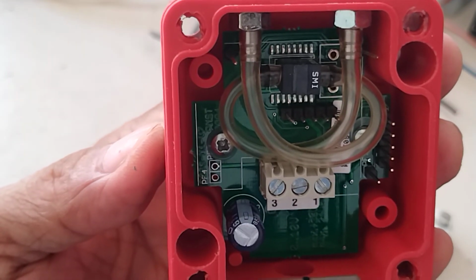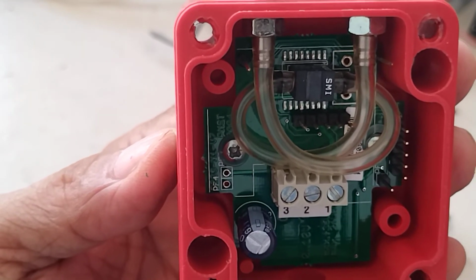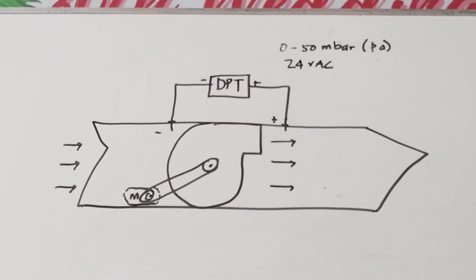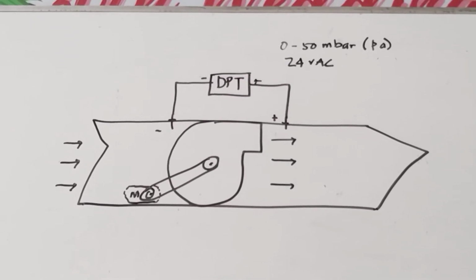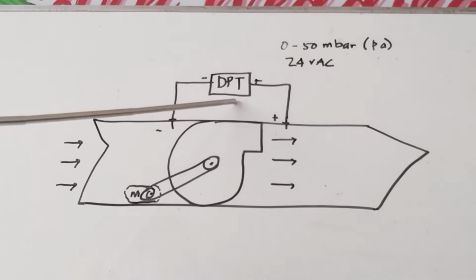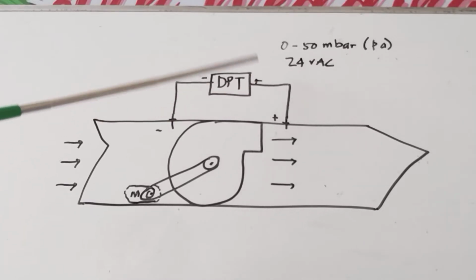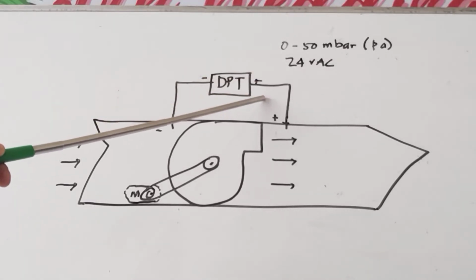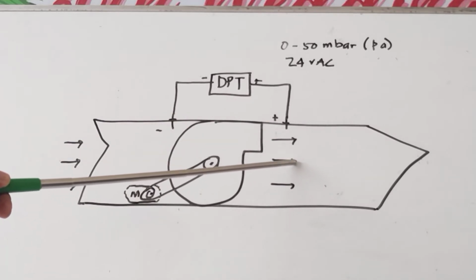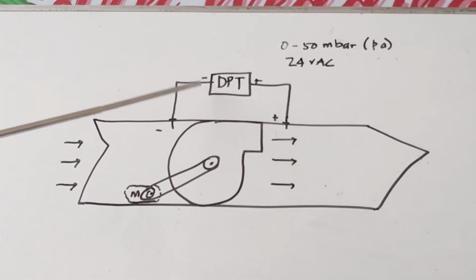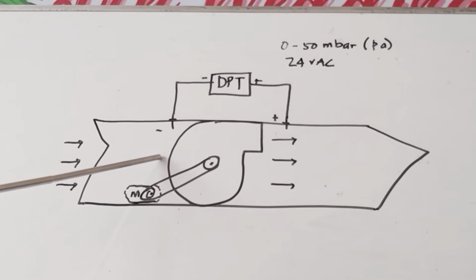Okay, so let me show you the drawing that I had prepared. Just give me a minute. Okay guys, so what I have here in my whiteboard is the guide on how you are going to install the differential pressure transmitter. Guys, so this is our DPT, okay? Likewise, the positive probe should go to the discharge side of the fan. Then the negative probe should go to the suction side of the fan, okay?